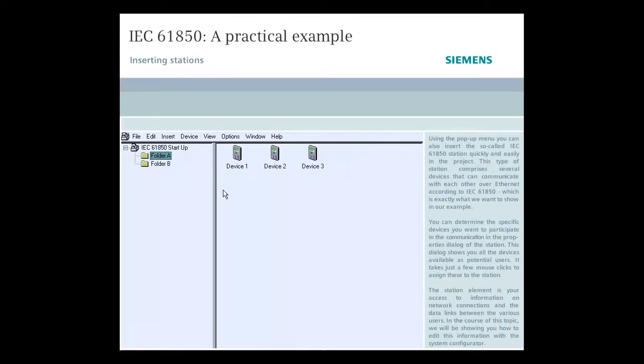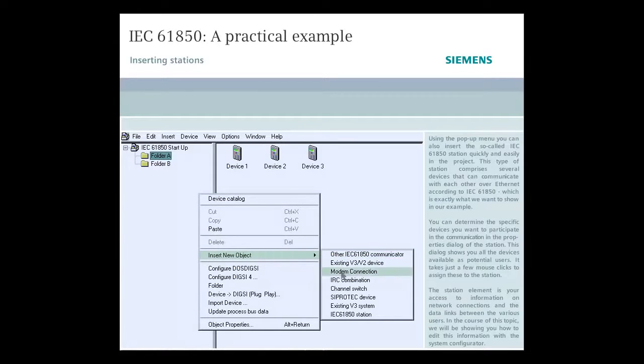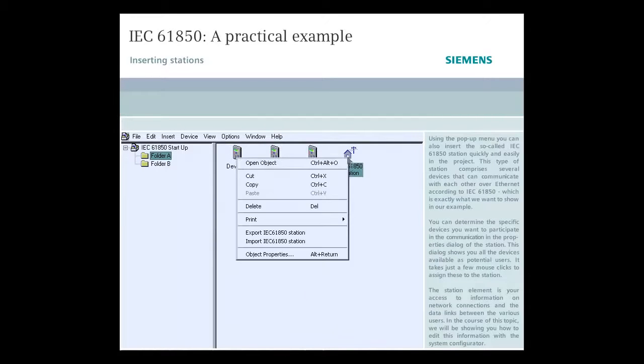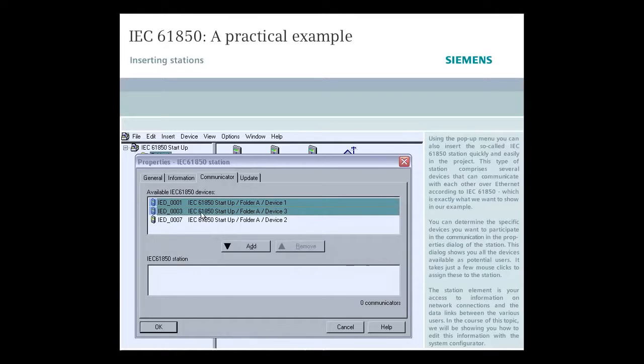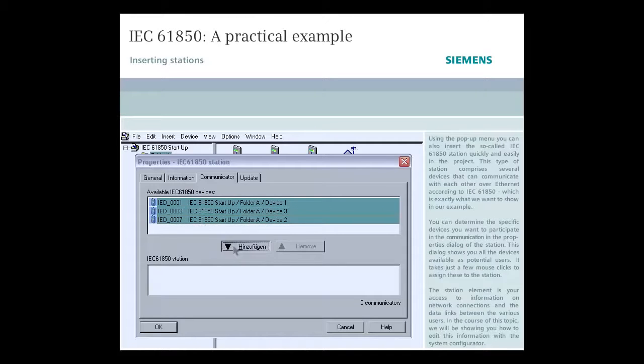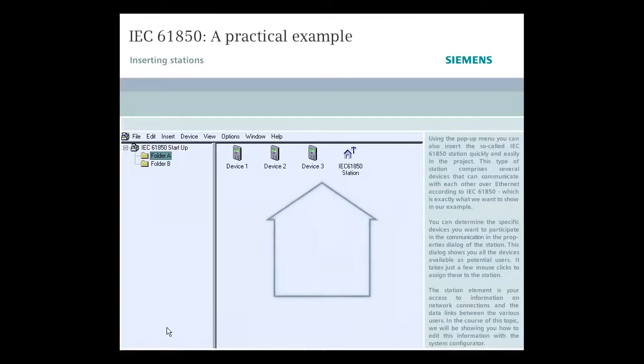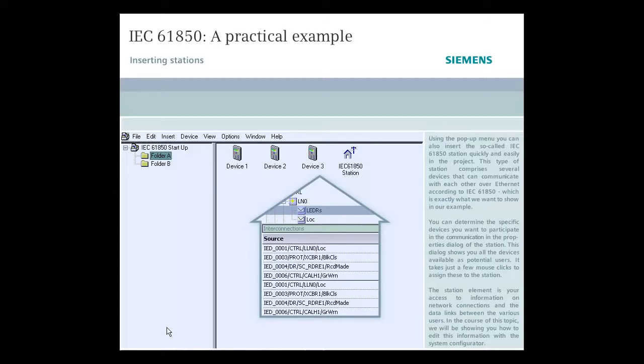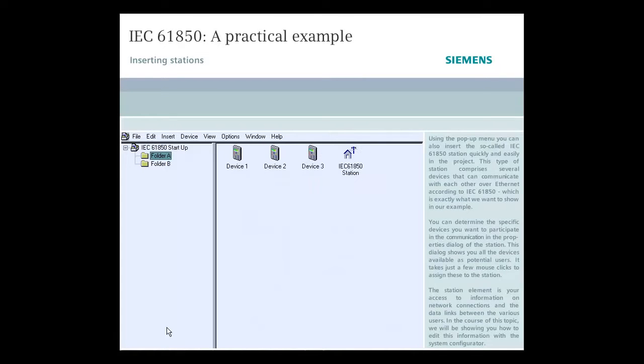Using the pop-up menu, you can also insert the so-called IEC 61850 station quickly and easily in the project. This type of station comprises several devices that can communicate with each other over Ethernet, according to IEC 61850, which is exactly what we want to show in our example. You can determine the specific devices you want to participate in the communication in the properties dialog of the station. This dialog shows you all the devices available as potential users. It takes just a few mouse clicks to assign these to the station. The station element is your access to information on network connections and the data links between the various users. In the course of this topic, we will be showing you how to edit this information with a system configurator.